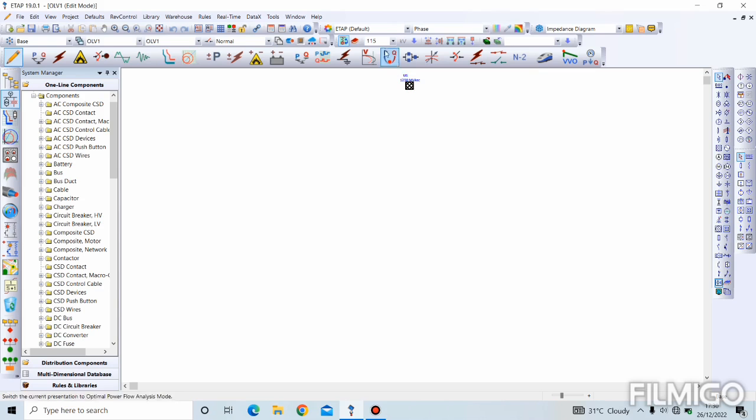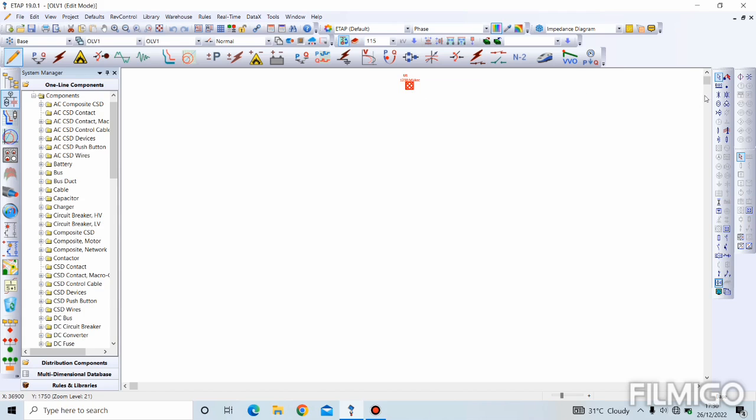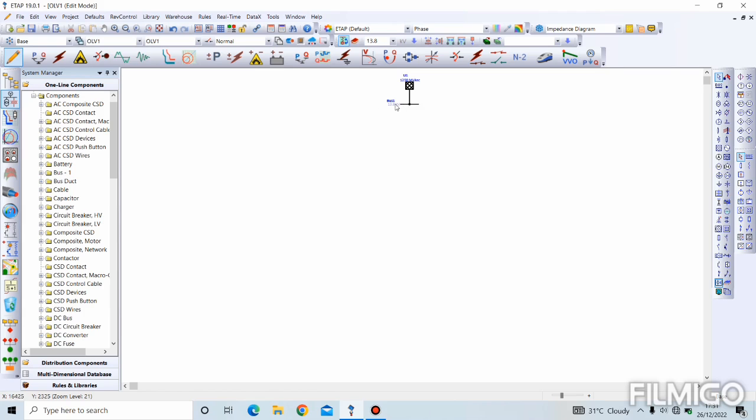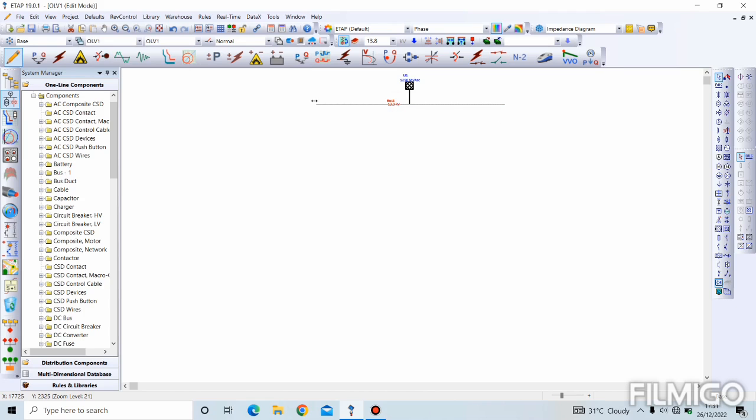Now, we want to connect a bus bar. See this part? KV to apply to selected bus. If we should use the auto build and click on a bus, the bus bar will automatically take this KV rating. Since we want our bus bar to be 13.8, all we have to do is to change this to 13.8. Then, we connect our bus bar. It automatically has the rating of 13.8 KV. Now, I'll be teaching on how to expand the bus bar. In order to expand the length of this bus bar, you click on it. Then, you take your cursor to the edge of the bus bar until it changes to a two-edged arrow. And you click and drag. You come over to this side and do the same thing. Now, we've extended the length of the bus bar.